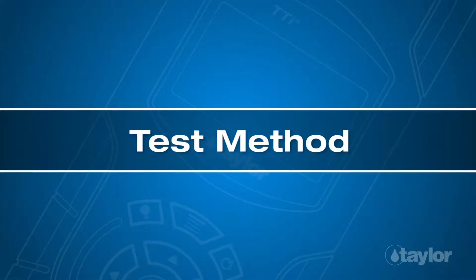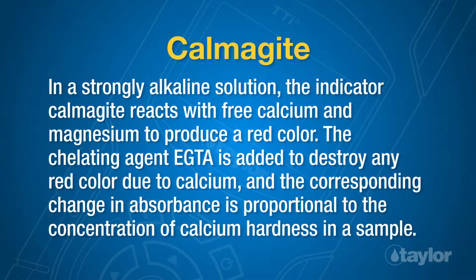Test Method — Calmagite. In a strongly alkaline solution, the indicator calmogite reacts with free calcium and magnesium to produce a red color. The chelating agent EGTA is added to destroy any red color due to calcium, and the corresponding change in absorbance is proportional to the concentration of calcium hardness in a sample.